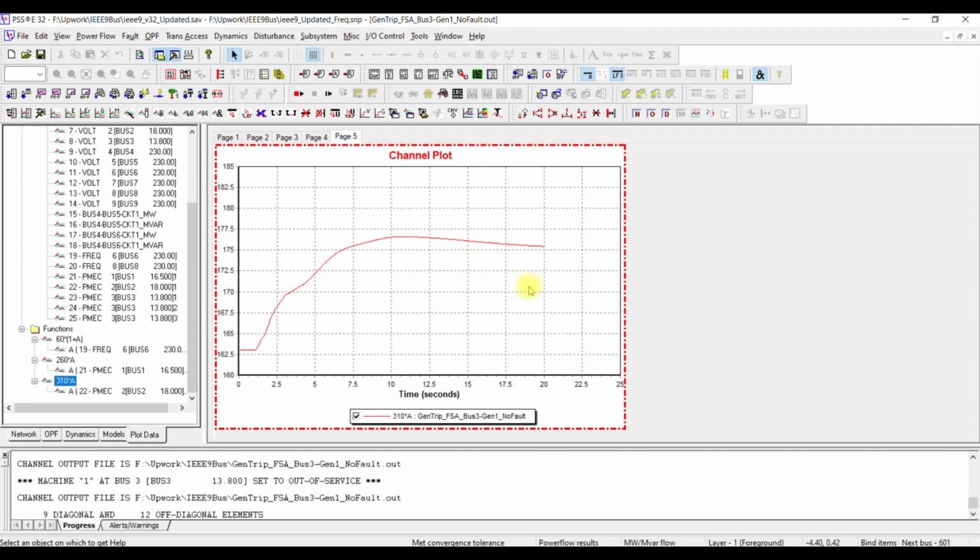In the same way, you can see for the gas turbine, and this is how your system reacts. So this is how, when the frequency was going down, the P mechanical sensed this change in frequency because its rotor speed will start to decrease, and with this rotor speed decreasing, the governor increased this P mechanical in order to compensate for the frequency.